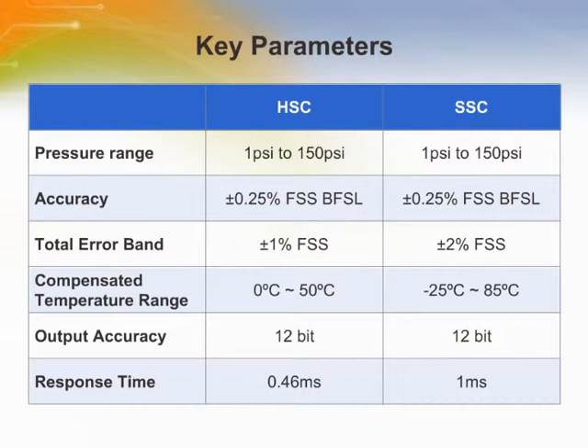The maximum deviation from the ideal transfer function over the entire compensated temperature and pressure range is called the total error band. These errors are caused by offset, full-scale span, pressure nonlinearity, pressure hysteresis, repeatability, etc. We can see from the table the HSC series has higher accuracy. If your application is more sensitive to response time, then the HSC is a better solution than the SSC.